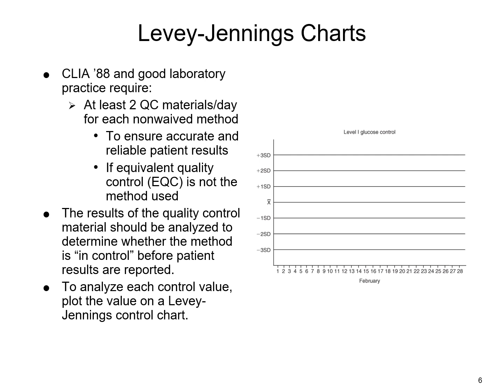and we're going to use the rules that are established by CLIA 88 in order to make sure that we are following what we need to. So CLIA does state that we have to use 2 levels of quality control material for each day of testing for anything that is non-waived. Now there are certain analytes that may require 3 quality control values. This is all going to be stated in the CLIA rules for each particular department. Also, your manufacturer is going to alert you to anything that needs to be done in addition. So your manufacturer may state that you need 3 levels of QC.